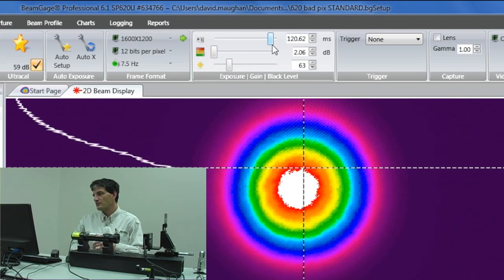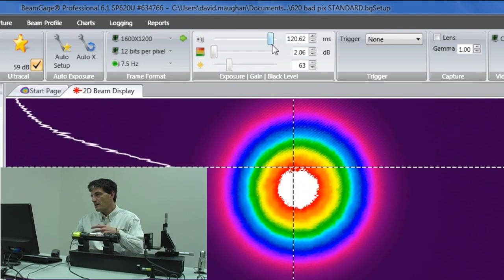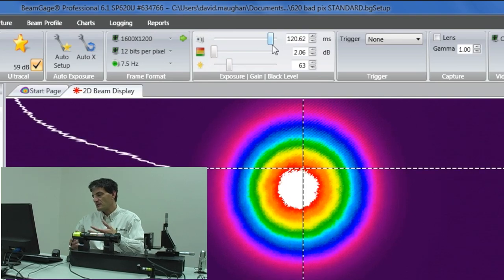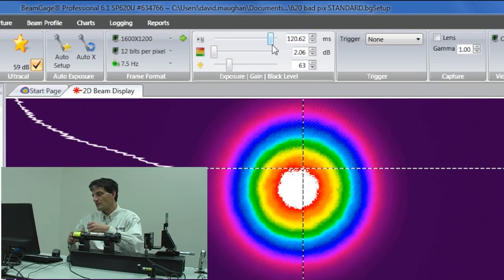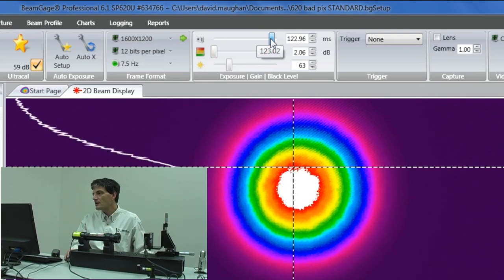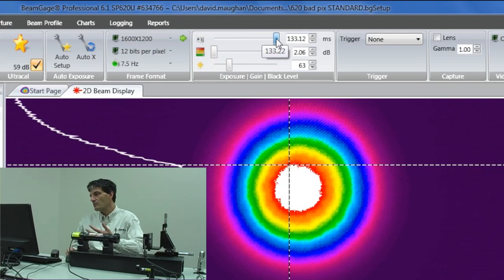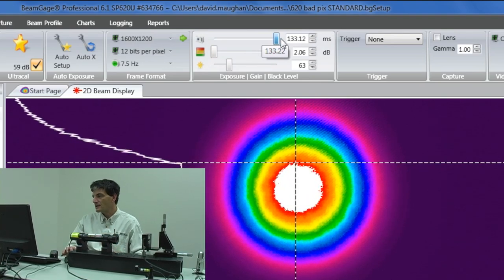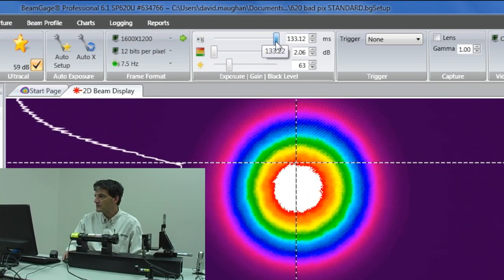The way this setting works is the camera, as charge builds up in each little pixel on the camera due to the light striking it, we wait a certain amount of time before we pull that charge off the camera. If I wait longer, what happens is more and more charge builds up and eventually I saturate the pixel array.